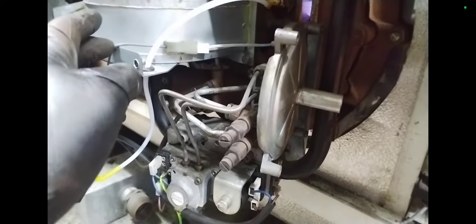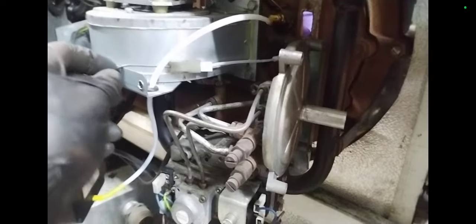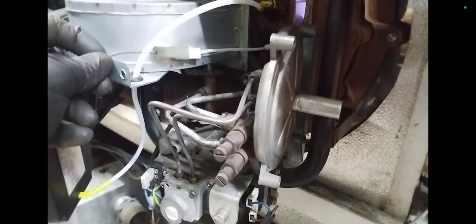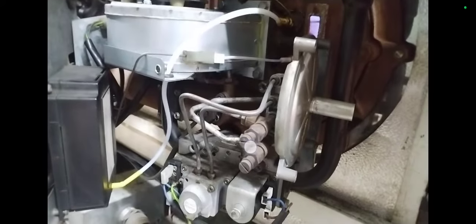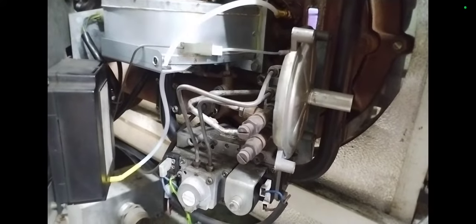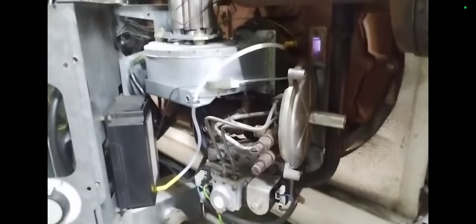trouble. From here is where you make adjustments to your pressure, your burner pressure, and there's your detection lead and there's your igniter. But I've had some where I need to make an adjustment because it's in the wrong place. So I turn it off. But I've had trouble with these. You can do your differentials from here. You can check your differential. It's supposed to be from there, and there you can attach. I think it's something, you look in the manual, but I think it's meant to be under about 1 millibar. The differential. It's not meant to be above it.